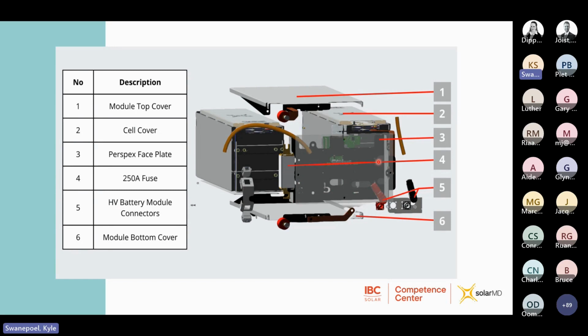It really does look quite impressive when you string a whole bunch of these batteries together, specifically in a container solution. It looks like Christmas has come early. And then each module is also fused. So there is a 250 amp fuse on the positive side. This we would generally refer to as an idiot fuse, because if you were to connect the positive and negative together on the module, it would cause a dead short and blow this fuse. But there is also protection here in the event of some sort of overcurrent occurrence happening on the module. And then each module has its HV connectors, and this is then for connecting the battery modules together in series, and then the bottom module cover as well.